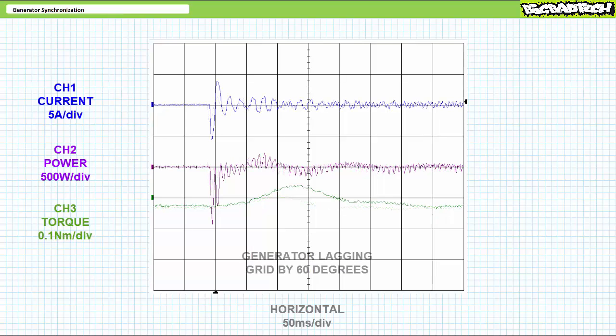Let's make it worse. Consider what happens when I close the contactor when the generator matches the grid phase shift, frequency, and voltage, however the rotor is an increased 60-degree lag behind the stator at the time of closure. As previously, electrically, there's a momentary surge of current and electrical power into the machine, only more dramatic in magnitude. Again, mechanically, the shaft experiences a surge of clockwise torque, only greater in strength. Given the rotor is further behind this time, the grid treats the lagging generator as a motor and gives it a strong yank forward. We are definitely in the danger zone now, both mechanically and electrically. A greater mismatch results in greater undesirable electrical and mechanical transients.